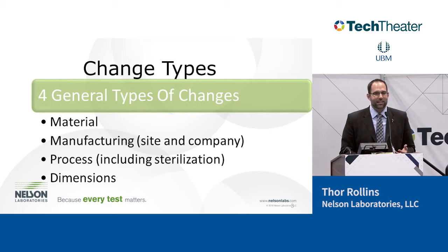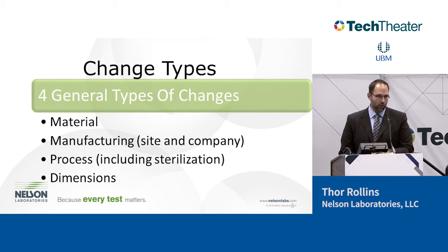That's why the FDA requires not just material evaluation but residual or cleanliness evaluation on medical devices. Most of the time when we see failures, it's not from the materials — it's from what's left on after manufacturing: oils, cleaners, things like that. We can use different techniques to evaluate a change, but you have to be smart enough to analyze what's happening and decide what testing to do to evaluate if that change has had an impact. Every change should at least go through an evaluation. Any change in your protocols should have a biocompatibility evaluation performed.